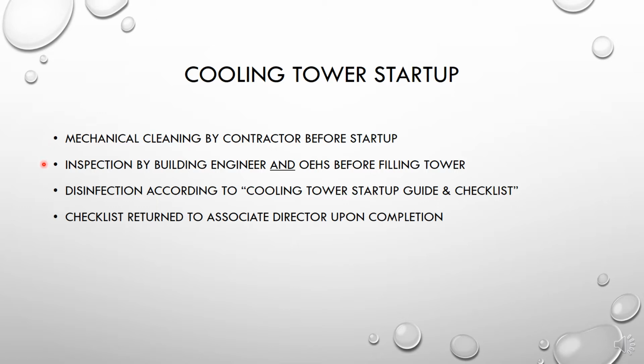Don't forget we need an inspection by the building engineer when the cleaning is complete, and my office. This doesn't have to be done together, to eliminate face-to-face interaction. I can talk to you on the phone or over email about your satisfaction with the cleaning, and then I will come on my own and take a look at the towers to make sure that it meets the water safety team's standards for cleaning. We do our disinfection according to our startup guide and checklist, which I'll cover here in a second, and then don't forget to turn that checklist back in to your associate director.